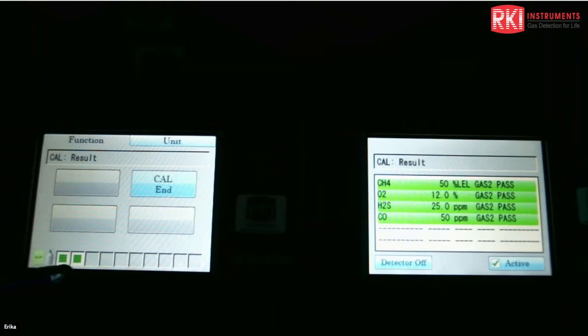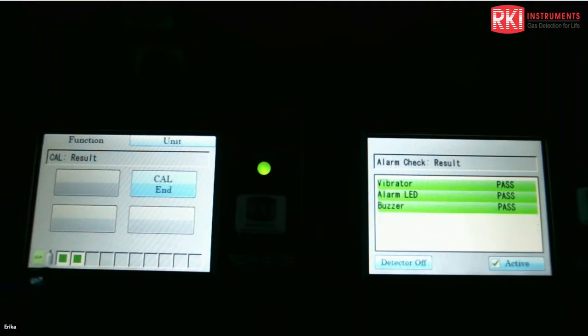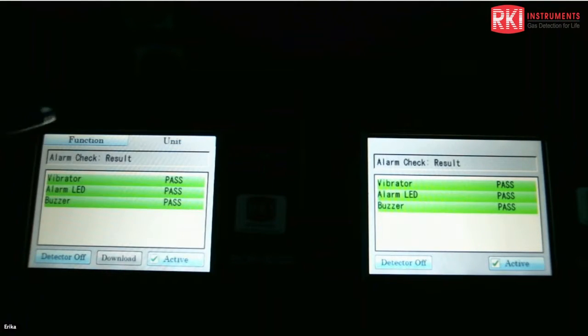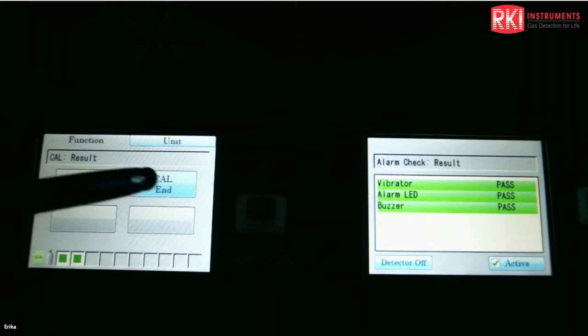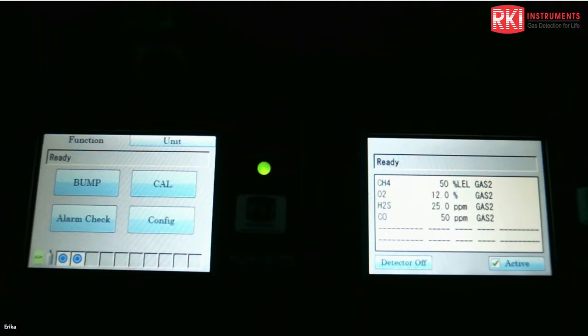There's also the two status icons over here. They were orange triangles before. Now they're green squares, which means the calibration passed. The orange triangle just means it's going through the calibration. So I'm going to hit cal end, and it's going to go back to the main screen again. That's pretty much how you would do a calibration.